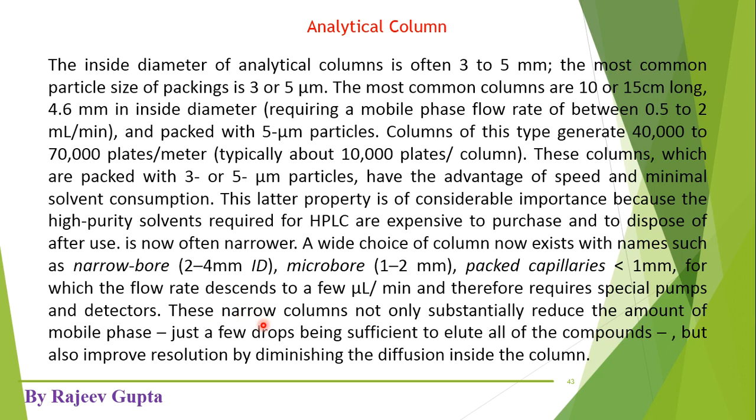As the inner diameter of the analytical column decreases, the consumption of our mobile phase also decreases. Just a few drops of mobile phase are sufficient to elute or separate all the sample components, and it also improves resolution by diminishing the diffusion inside the column.